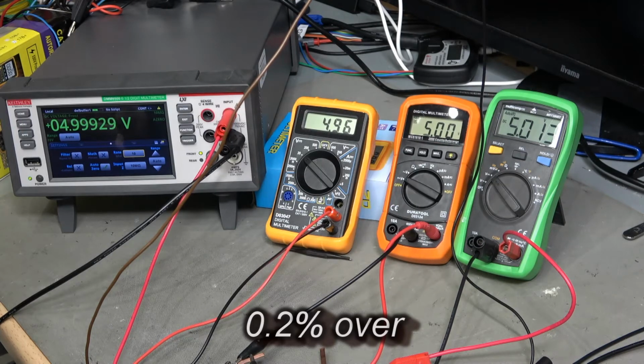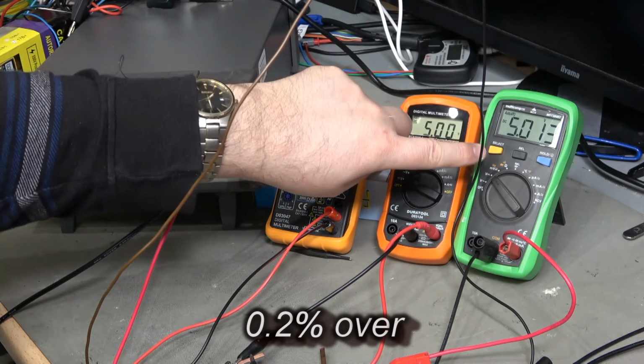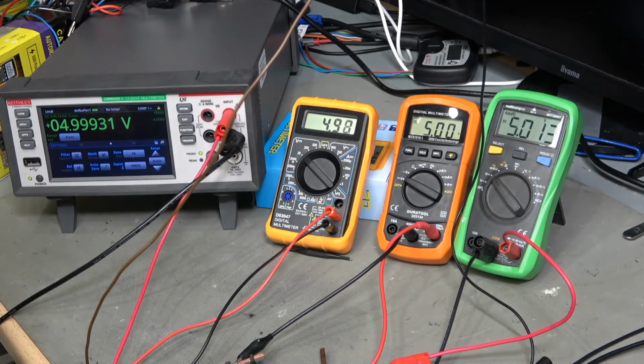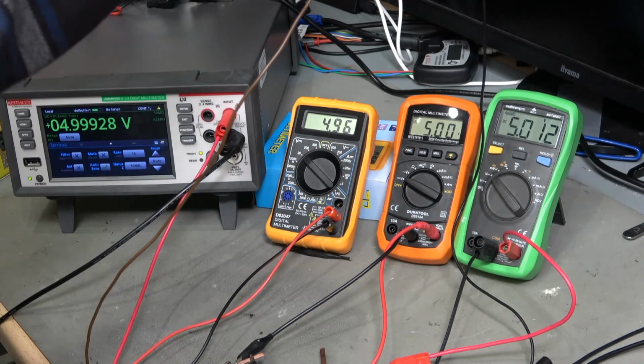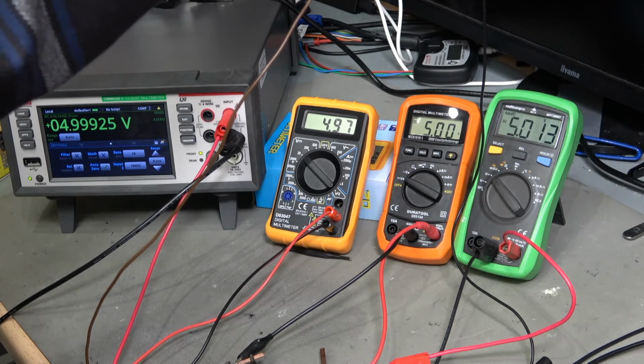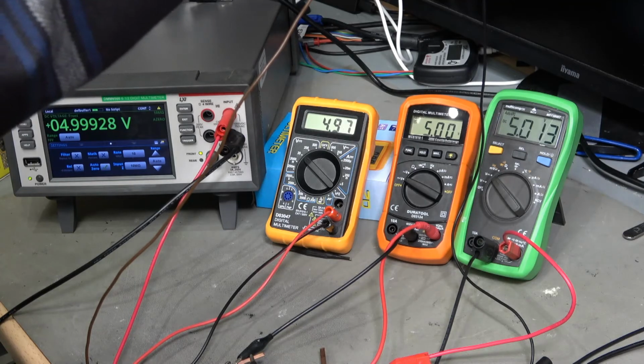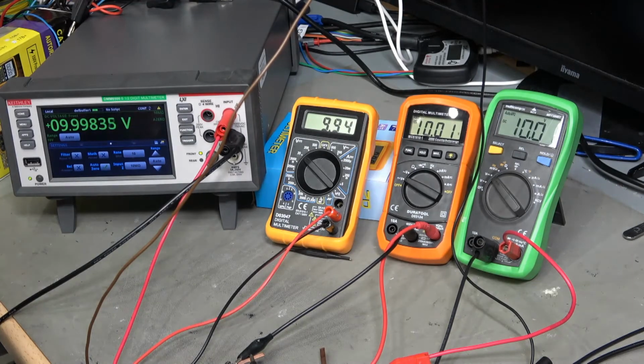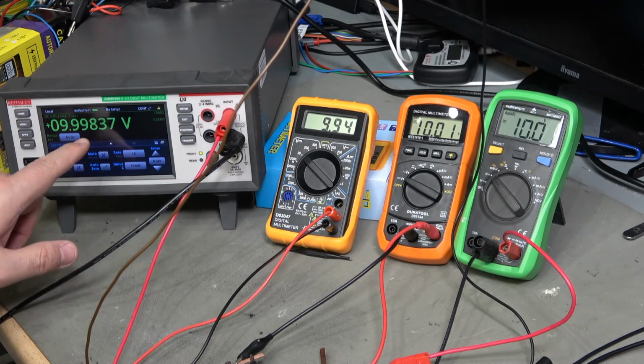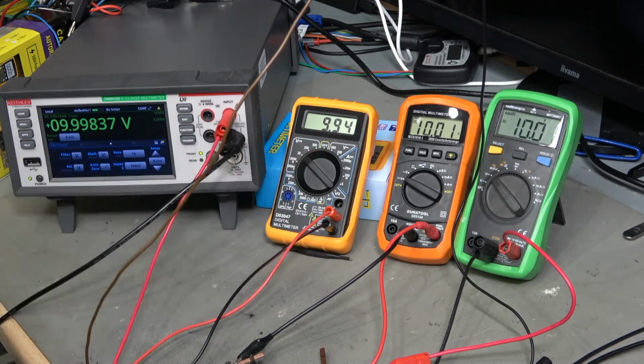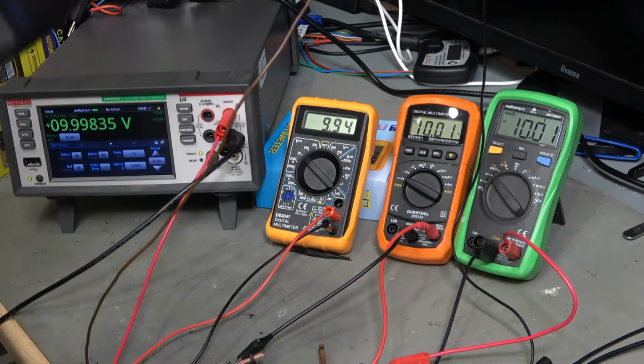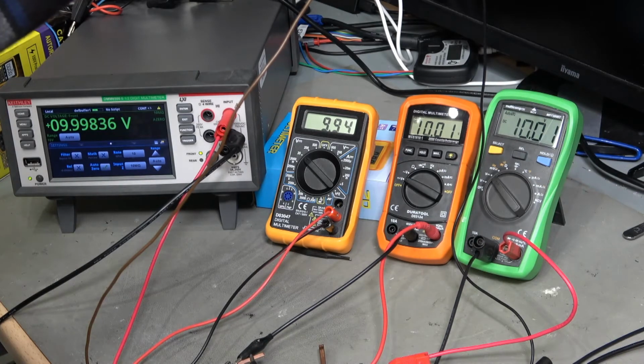So I can do, yeah, 0.2% error on that one. So yeah, essentially no error on that one at all. Let's wind it up to 10 volts. So I'm not going to go through the palaver of looking at every single measurement with you on this. We can see here we've got 9.94, 10.01 and 10.0. So these are all pretty much on the money again. Even the 9.94 is within 0.6%, so no big deal really. Okay, so let's turn this up to 12 volts now, because 12 volts is a value you would use quite a lot.